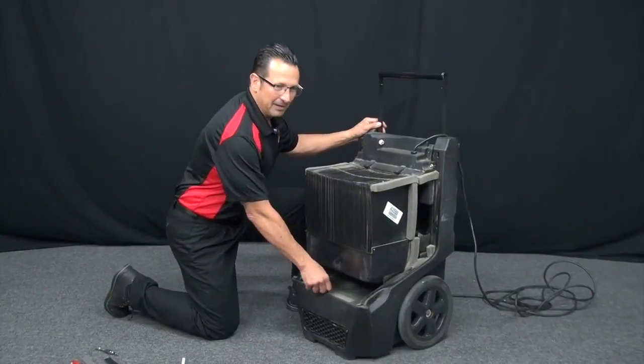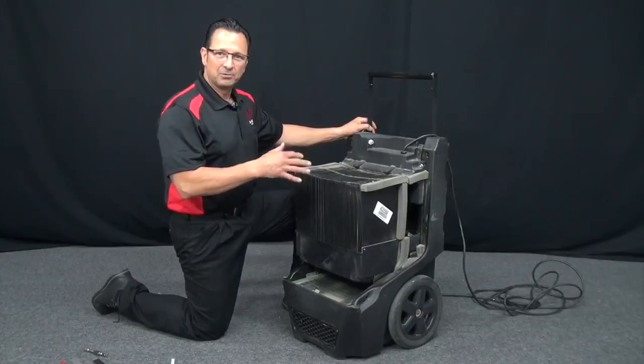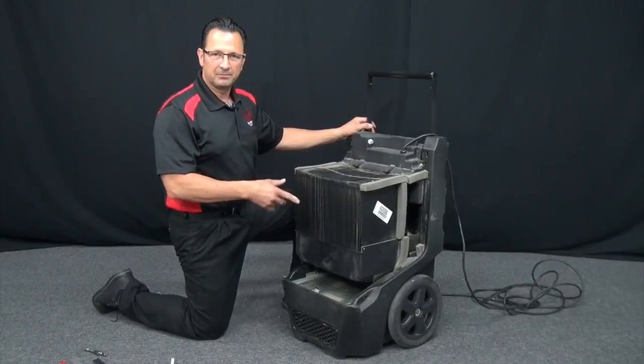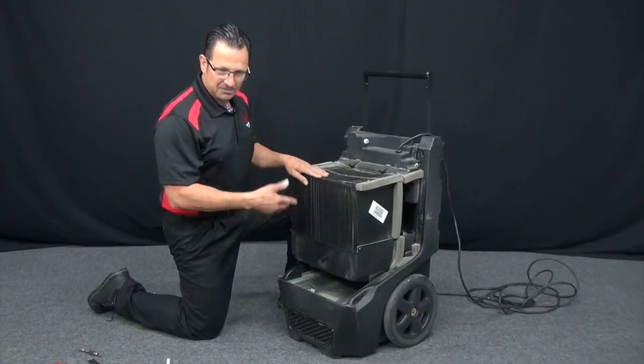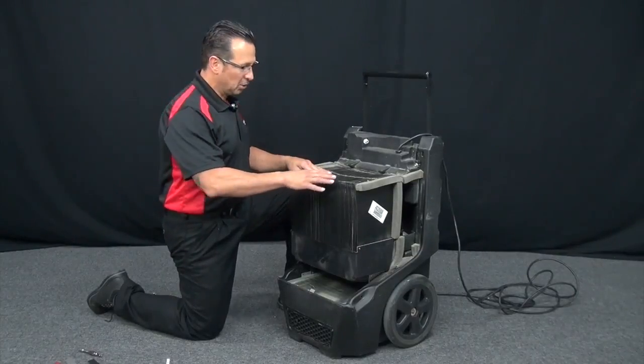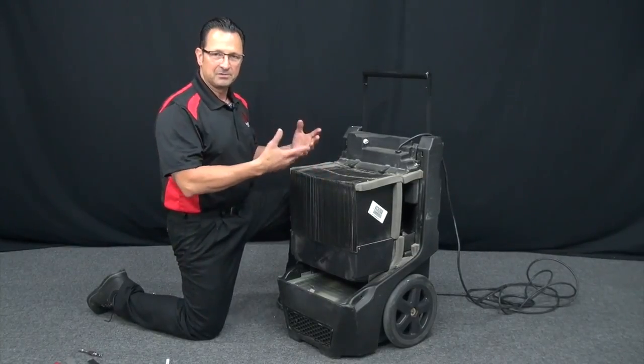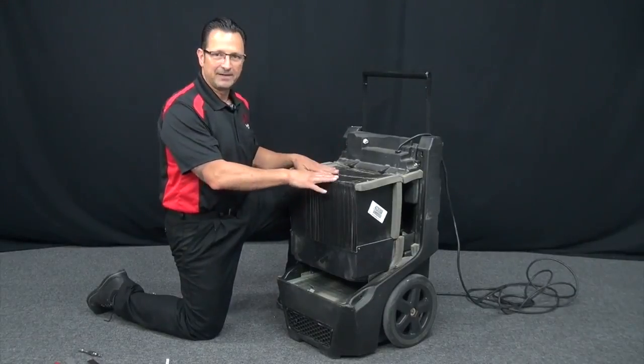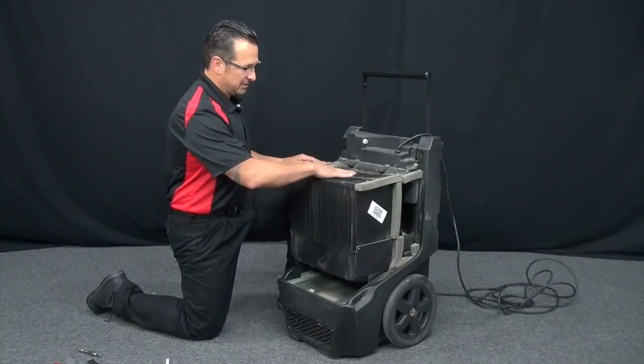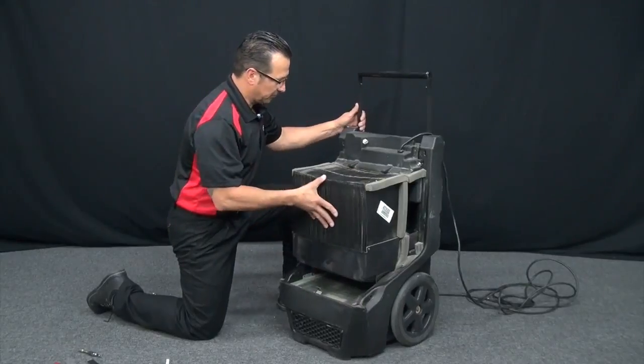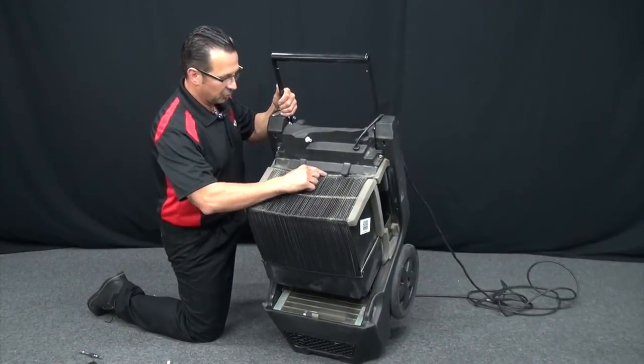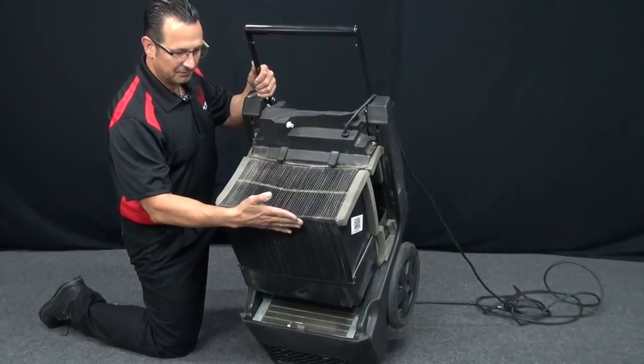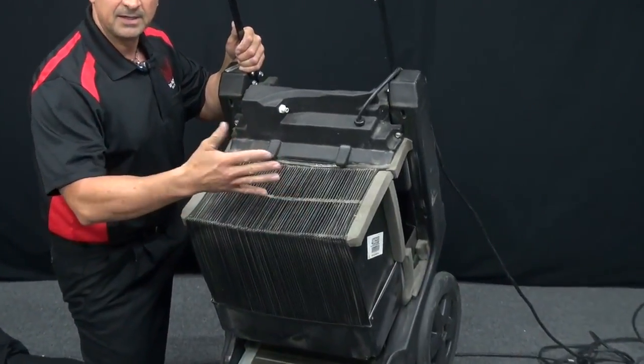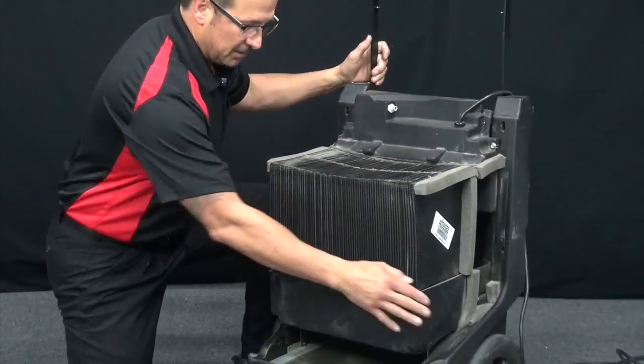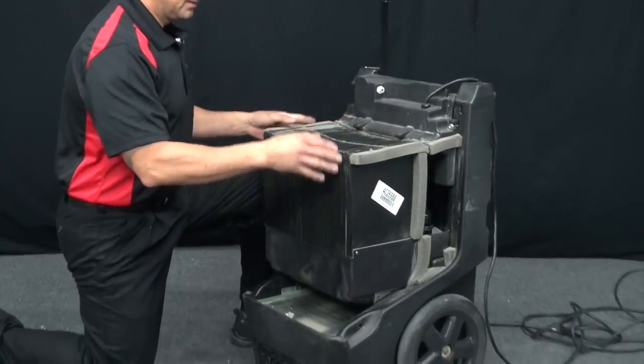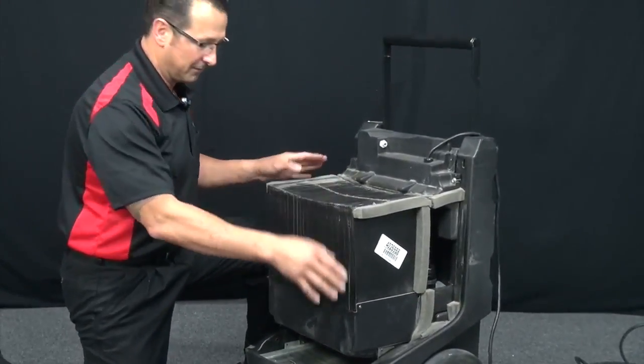Today I want to talk to you about an update that Phoenix has done over the years on the R200 and the R175. And what this is, a heat exchanger support. Over time, due to the temperatures and certain conditions that we use these dehumidifiers in, it will cause the heat exchanger to sag, creating perhaps a large opening in the back of the heat exchanger and also in the front between the heat exchanger and the front cover. So we came up with these supports that keep that from happening any further.